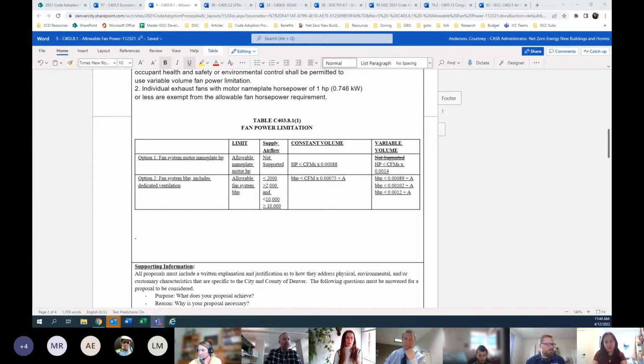Do we want to write an exclusion to address that, but still have it for the new buildings? I'd like to hear John's input, since I brought this up while reviewing the proposal. I think we could write an exclusion, but we still need to set limits, so I don't know if just the base code fan power limitation is okay for equipment replacement. Then for new buildings it goes to this additional requirement, which seems kind of awkward to have both still available.